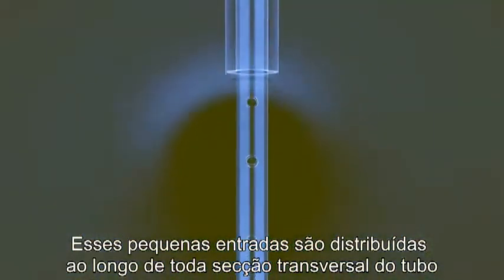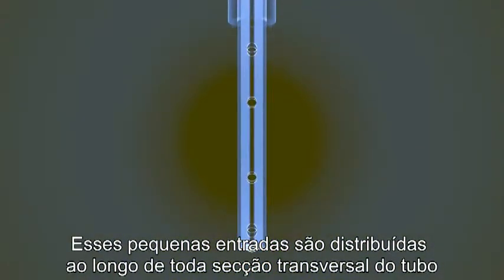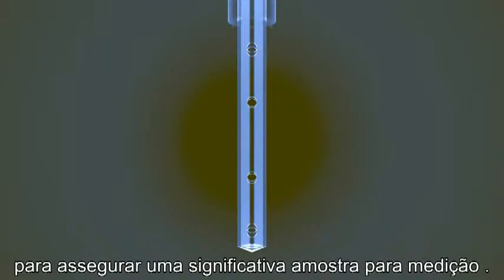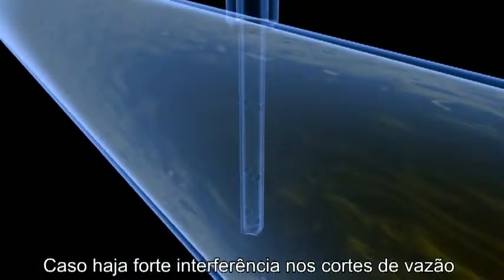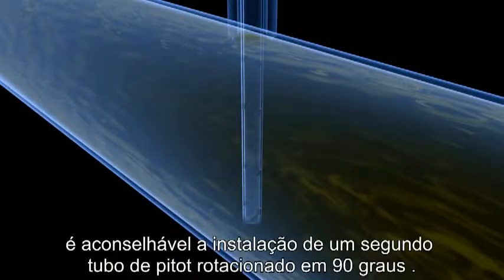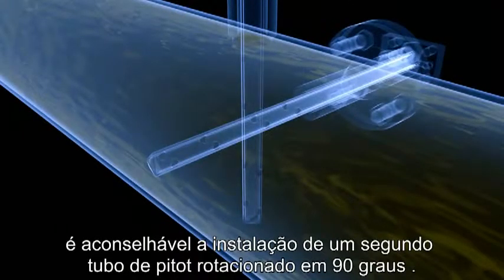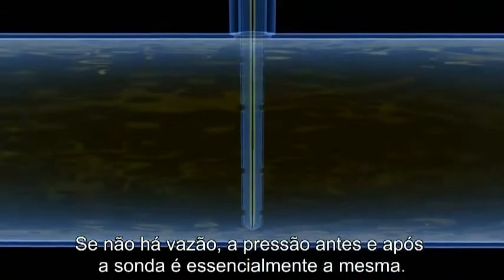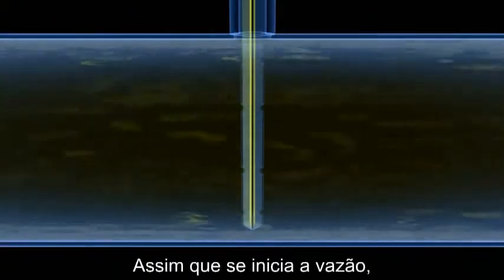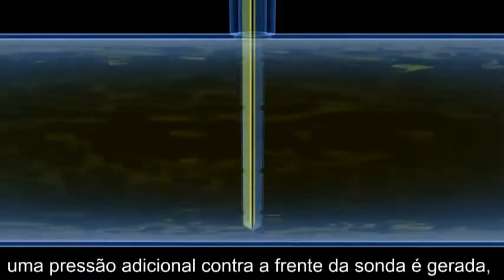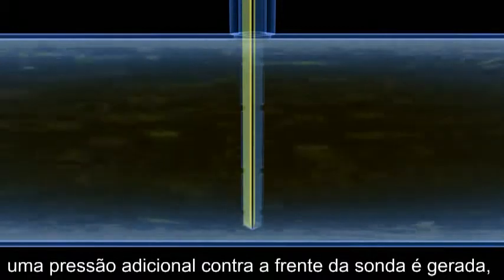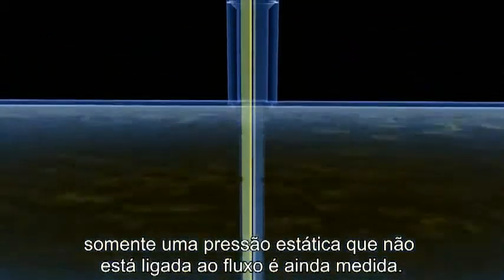The individual pressure taps are distributed along the entire pipe cross-section to ensure a representative measurement. If there is strong interference in the flow profiles, it's advisable to fit a second pitot tube, rotated by 90 degrees. If the fluid is not flowing, the pressure before and after the probe is essentially the same. As soon as the fluid starts to flow, an additional impact pressure against the front of the probe is generated, also known as the dynamic pressure. On the rear of the probe, in contrast, only the static pressure, which is not related to the flow, is still measured.